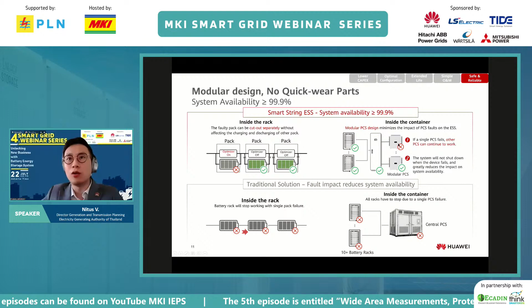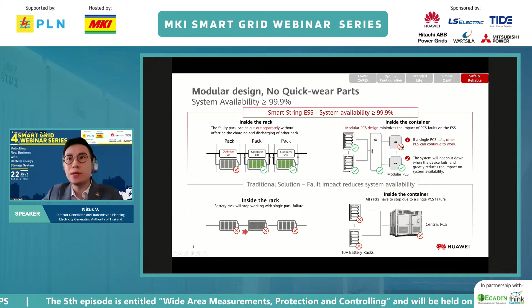Secondly, consider the PCS. Traditionally you deploy one very large PCS in the megawatt size, but this causes a problem: once this central PCS goes down, it causes 10-plus battery racks to stop producing power because the link is broken. In comparison, with smaller PCS units—like ours, 200 kilowatt each—connected in parallel, even if one PCS fails, you only lose 200 kilowatts.